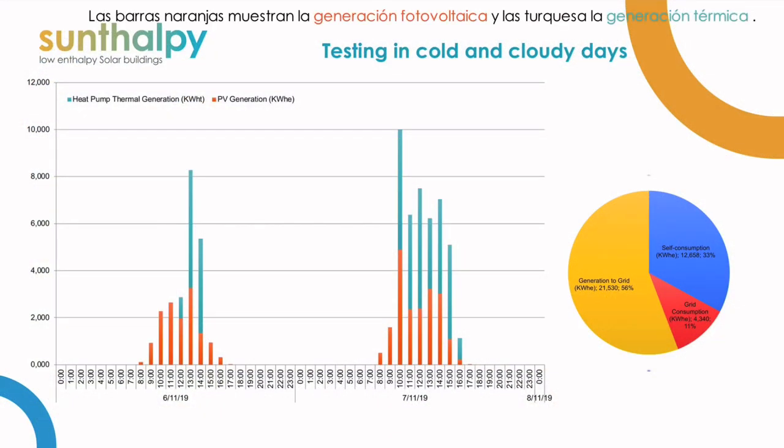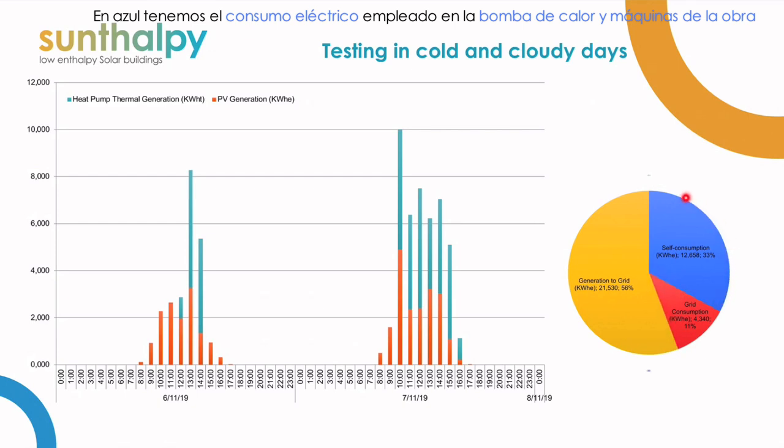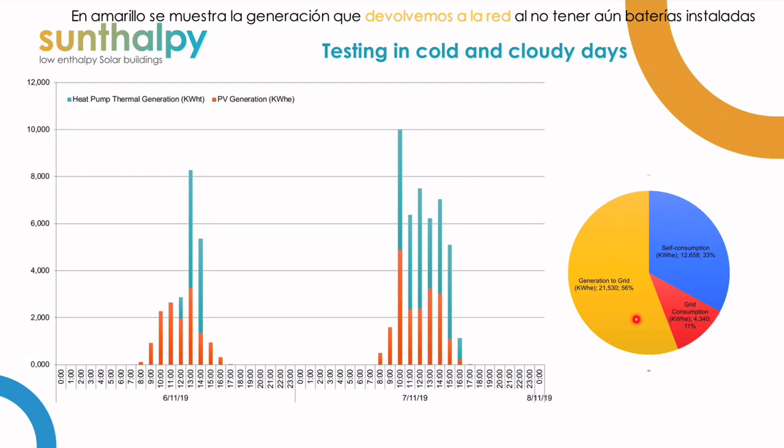The bar graph shows the photovoltaic production in the orange bars and the heat pump production in the teal bars. The graph on the right shows the accumulation for the two days. In blue, we have the photovoltaic production which has been used for the heat pump and the other electrical devices like the cutting and mixing machines that we are still using at the final stages of construction. In yellow, we see the photovoltaic production we sent to the grid to cover the very little electricity we took from the grid at night, because we still have not installed the lithium batteries.